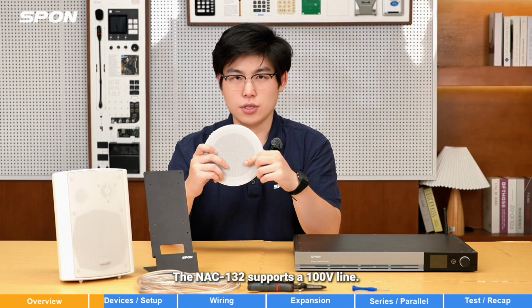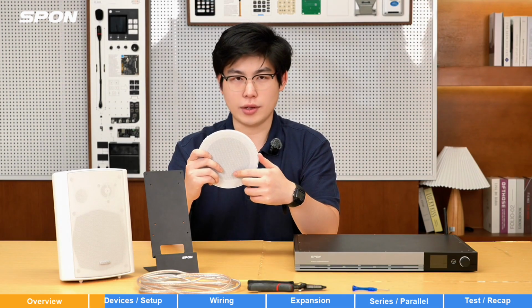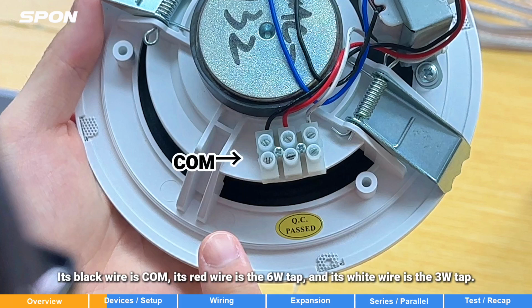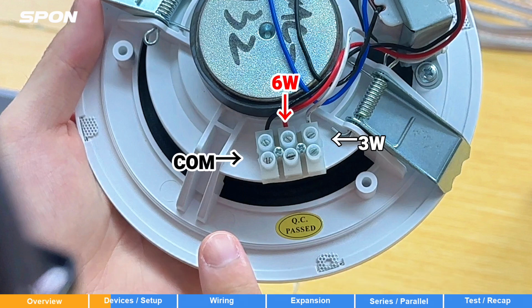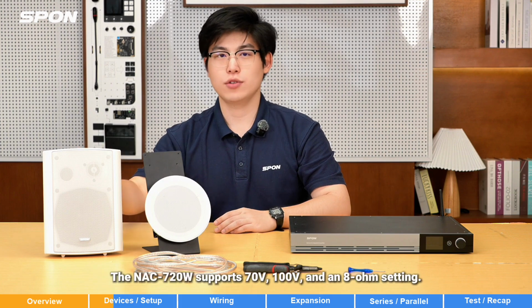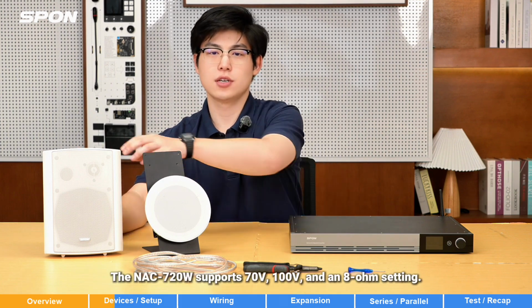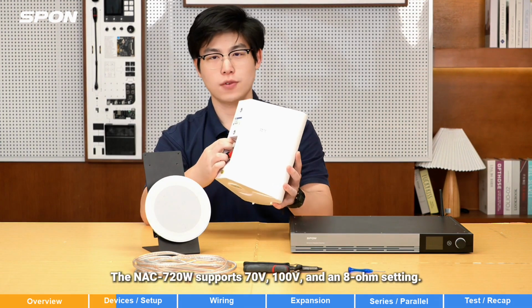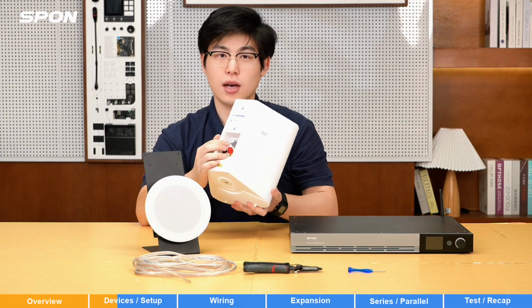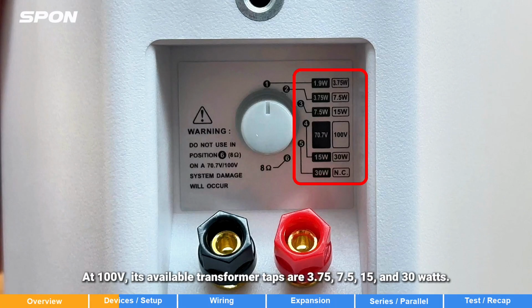The NAC-132 supports a 100 volt line. Its black wire is COM, its red wire is the 6 watt tap, and its white wire is the 3 watt tap. You can find this information in the product menu. The NAC-720W supports 70 volts, 100 volts, and an 8 ohm setting. At 100 volts, it has transformer taps at 3.75, 7.5, 15, and 30 watts.